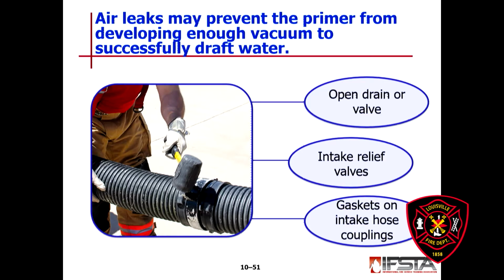So when we put the pump into operation, for two-stage pumps the transfer valve needs to be in volume. We're going to operate the priming control. Make sure the pump's airtight. Set our engine RPMs, as I said. Operate the primer control. As air is evacuated from the pump, the master intake gauge will register a vacuum. As the primer operates, the vacuum reading should increase as atmospheric pressure forces water into the intake hose.